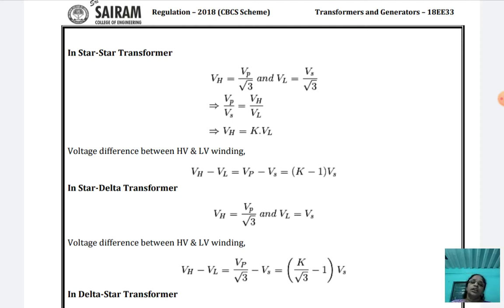This is in the star connection. The phase voltage is equal to VL by root 3. So VP and VS are the primary voltage and the secondary voltage, with each phase voltage being the line voltage divided by root 3. Normally in a star connection, phase voltage is equal to VL by root 3. Similarly, VP means primary voltage, VS means secondary voltage. Therefore VP by VS equals VH by VL, so VH is equal to K into VL.